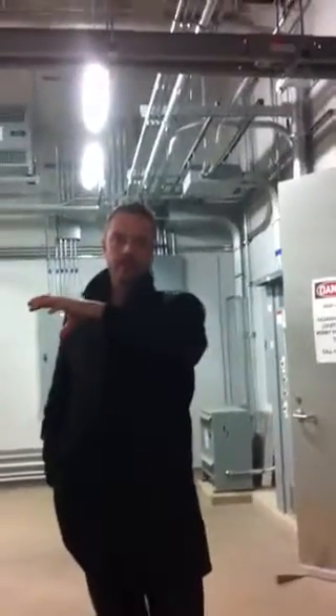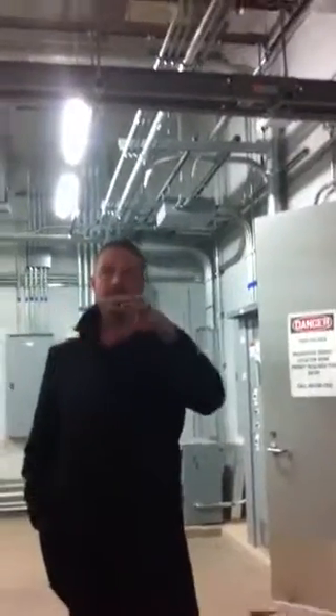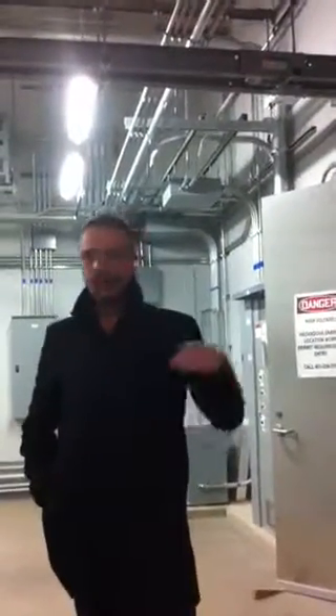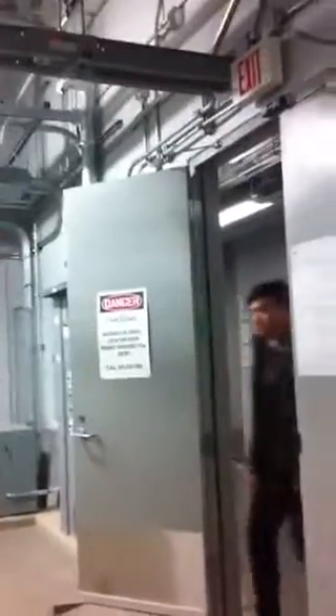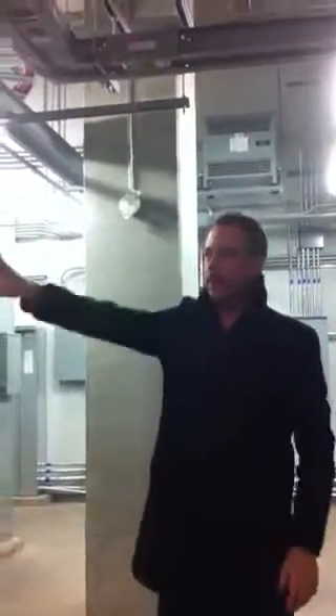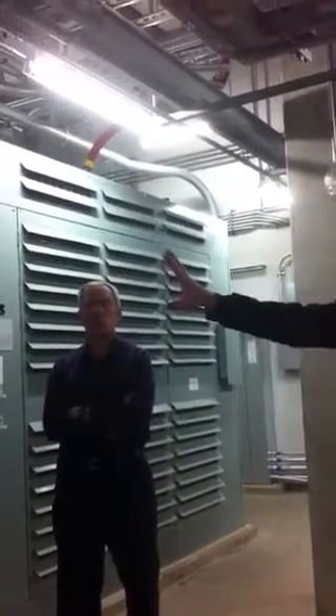So what we've got in the new loading dock area, which sits just on the northwest side of C block, there's a large transformer room. Similar to this, a large transformer room, transformers are the same, high voltage gear is the same. Because we were dealing with an existing facility, we actually have our 2 transformers and our high voltage gear in one room, and they feed the 600 volt distribution board, which in that building is significantly bigger than this physically, just because there's far more feeder breakers, sits in another room.